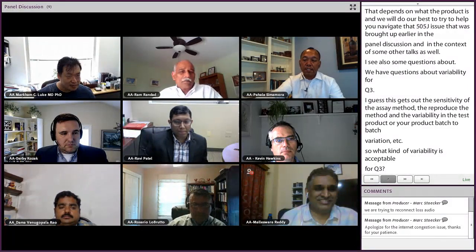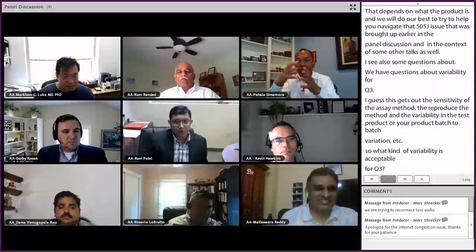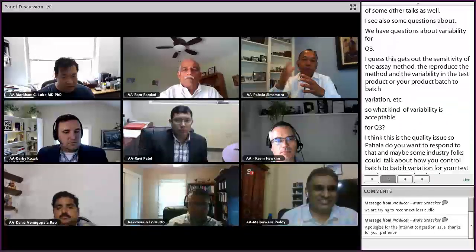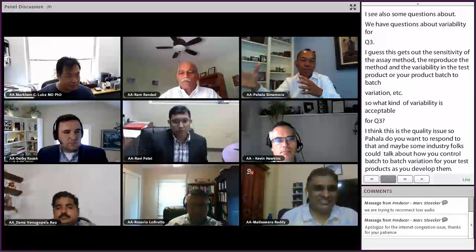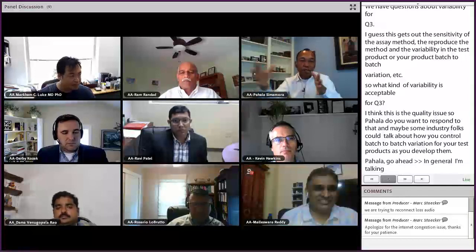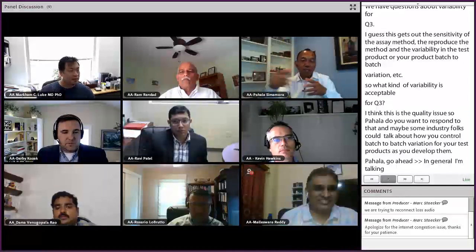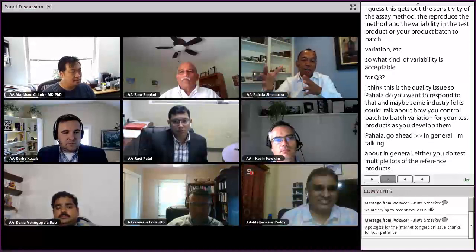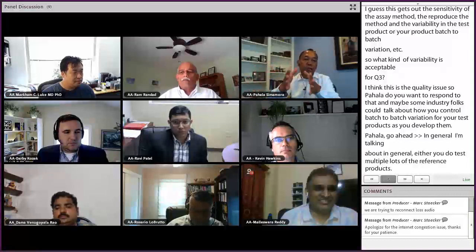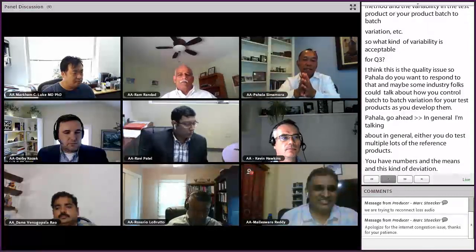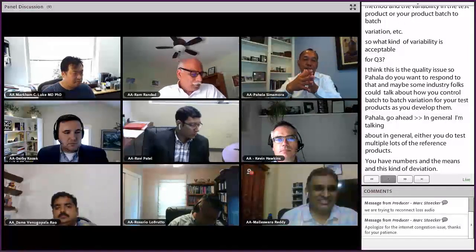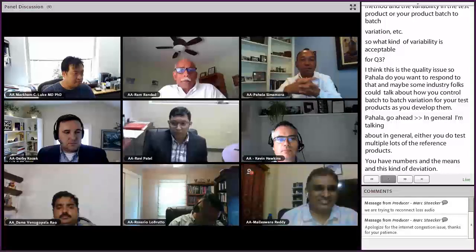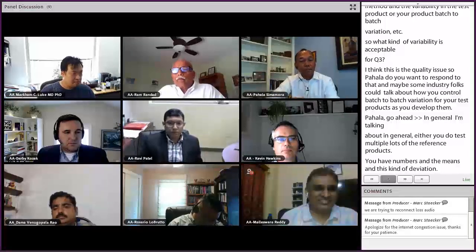Sure, Mark. In general, when you test multiple lots of the reference product, you get numbers, the range, the mean and the standard deviation, and then you have the guide for where the property of interest needs to be. In general it should be within this variability of the RLD, the reference product numbers.